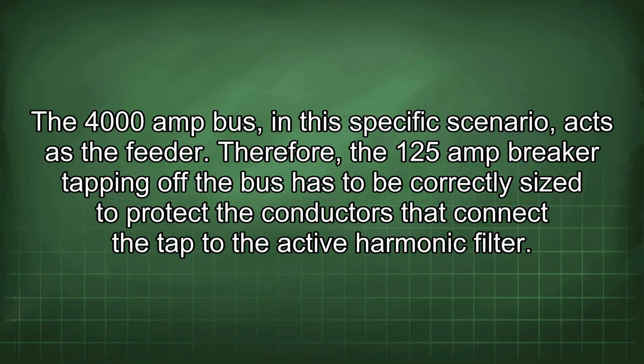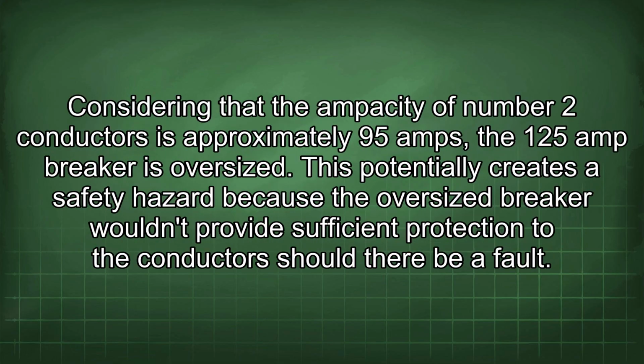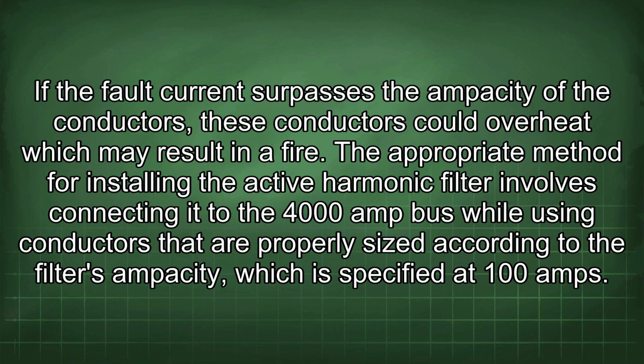Therefore, the 125 amp breaker tapping off the bus has to be correctly sized to protect the conductors that connect the tap to the active harmonic filter. Considering that the ampacity of number 2 conductors is approximately 95 amps, the 125 amp breaker is oversized. This potentially creates a safety hazard because the oversized breaker wouldn't provide sufficient protection to the conductors should there be a fault.